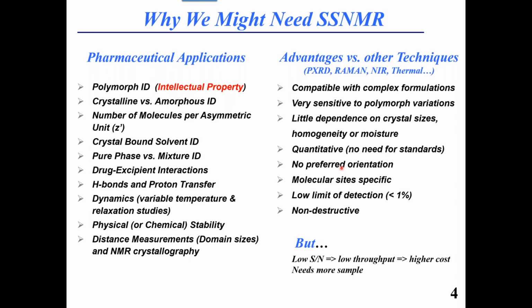I should say that in X-ray, the origin of preferred orientation is well known. It's the preferred orientation of the particles, and the solution is also well known: grinding. But as simple as it sounds, you never know, especially on a new project with new samples, how much grinding is necessary. If you grind too little, you're not going to remove the preferred orientation.